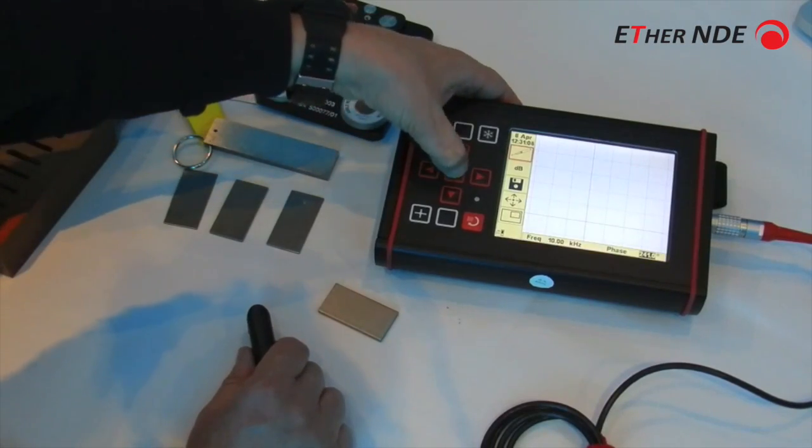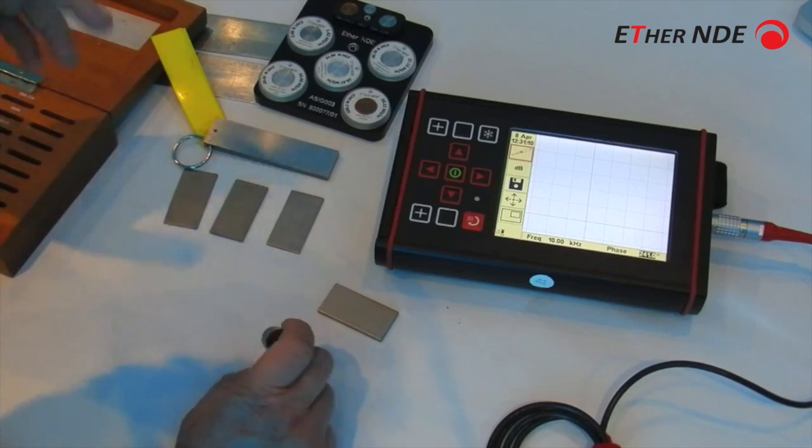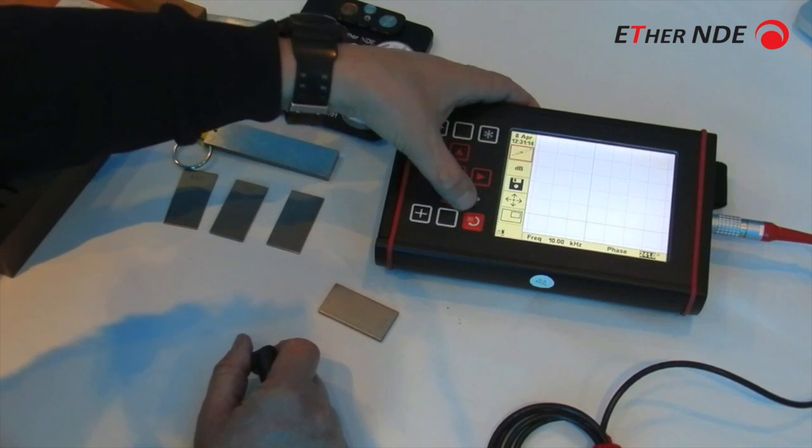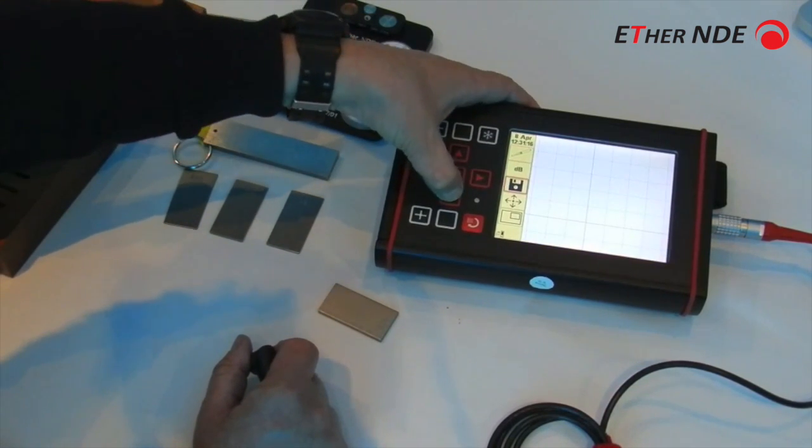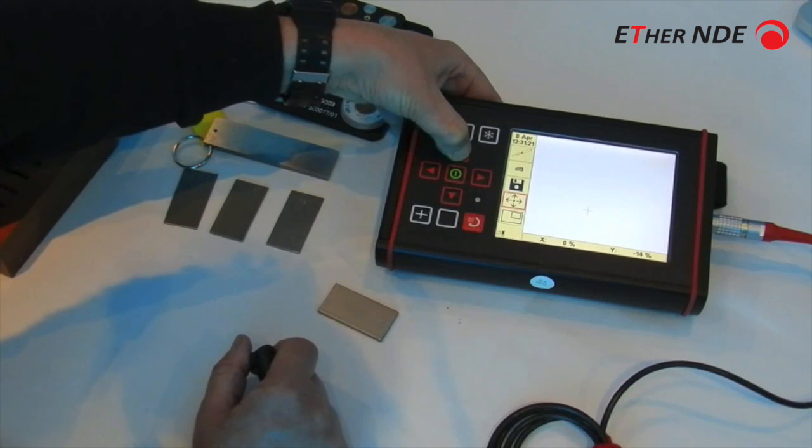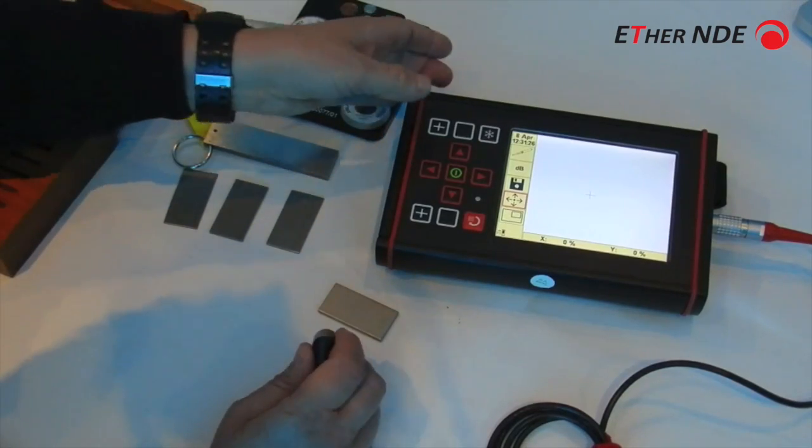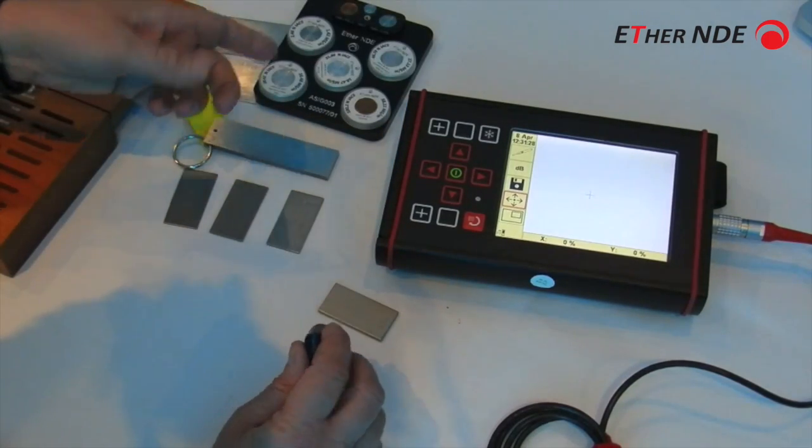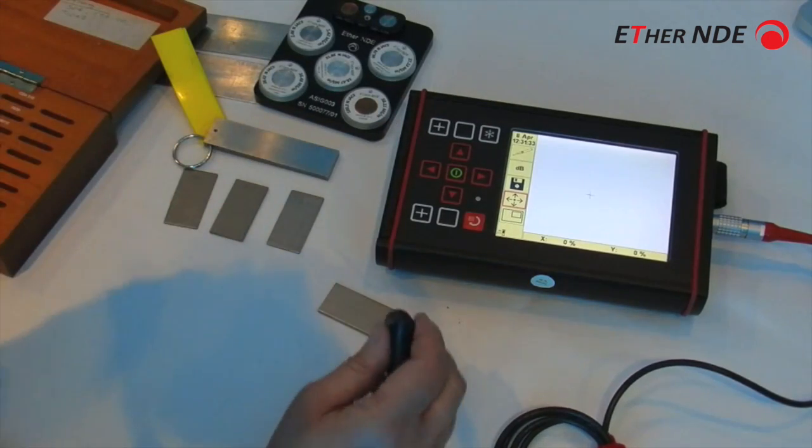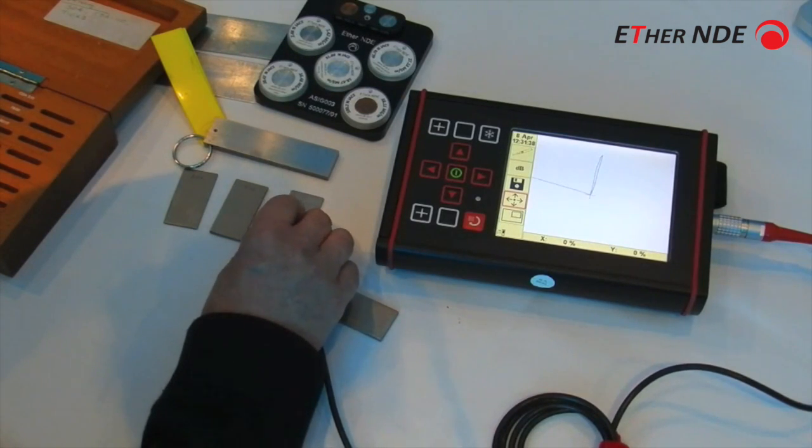Here I've set the probe frequency to 10kHz, because that, from experience, is quite good for doing various material sorting. It might be a good idea to move the spot to the middle of the screen, so let's go and do that. So there's 0, 0. Now, if I balance in air, like we saw with the aluminium, we get various liftoff lines.